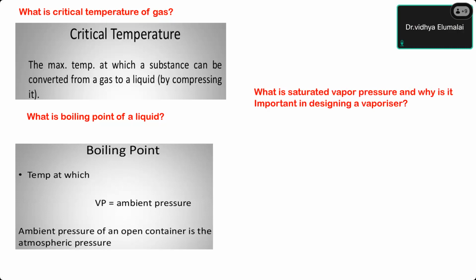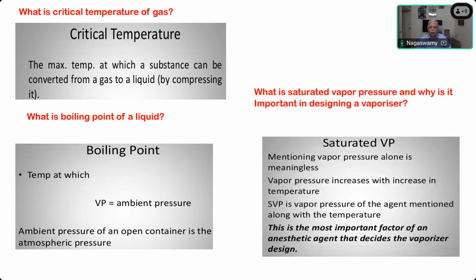It is the equilibrium pressure above which the vaporization cannot occur. Somewhat saturated vapor pressure. Mentioning vapor pressure alone is meaningless because vapor pressure increases with increase in temperature. So saturated vapor pressure is the vapor pressure of the agent mentioned along with its temperature. It is the most important factor of an anesthetic agent that decides the vaporizer design. That means it is at equilibrium with the fluid. Okay.